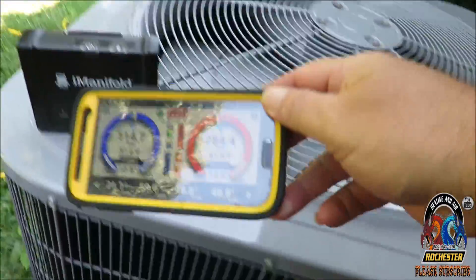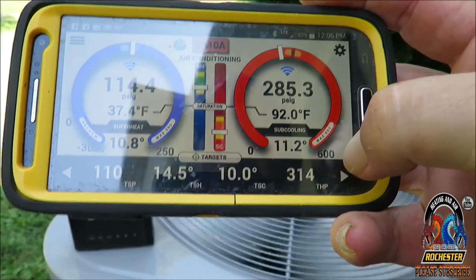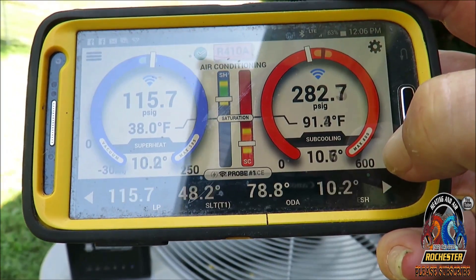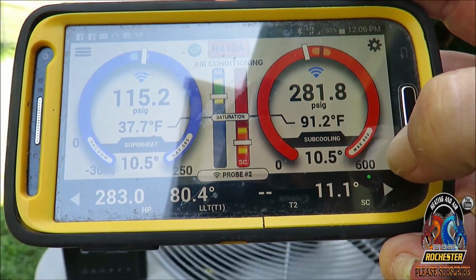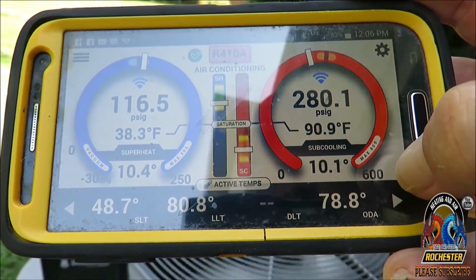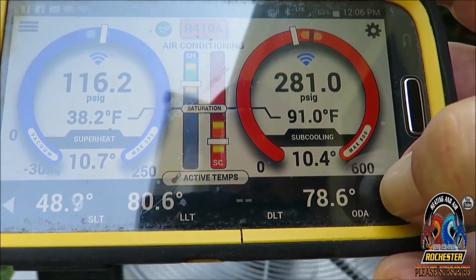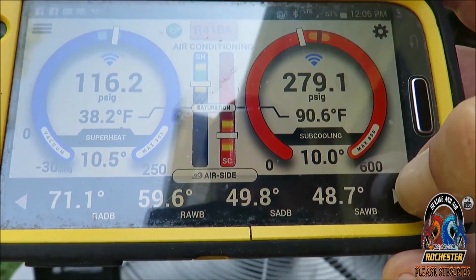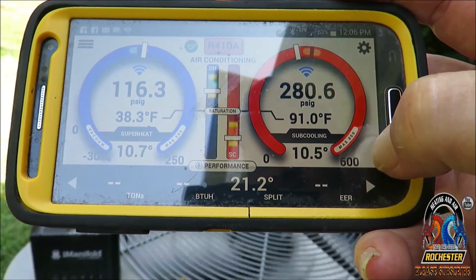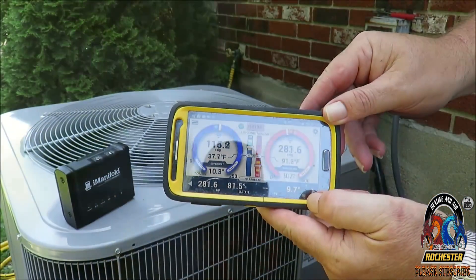Looks like we're pretty tuned in here. We're getting our 10 degrees subcooling, so let's rifle through it real quick. I know that split's a little high, but a lot of the trunk work is down there in the garage. Reading 21.2 — I think we're good for now.